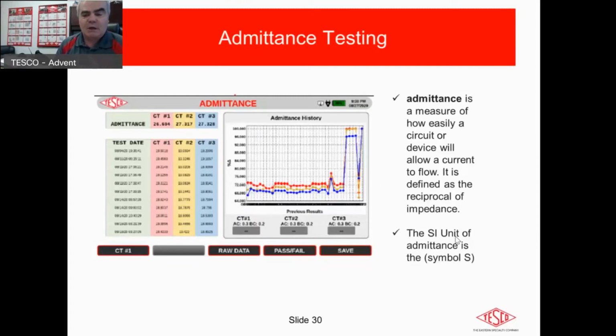And that means an electrician hasn't been in there messing around trying to hook up some new part of the plant or some new lighting services or whatever. There's no broken wires, there's probably no loose wires, there's no additional corrosion. All of the things that, as John was talking about before, burden, all of those things can add burden to your circuit, which as we know, once you get over that knee, as you saw on the chart a few slides back, your accuracy drops way off.